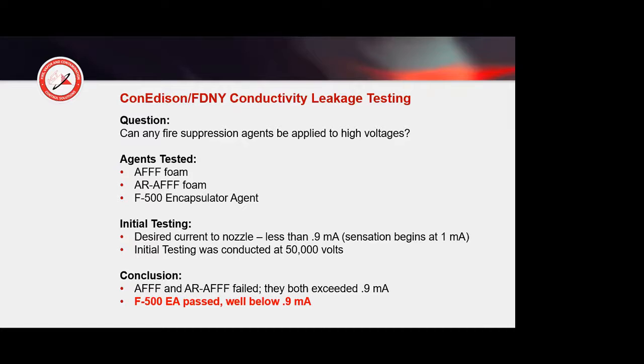When you put F500 into the stream at 3%, if you spray it on in a smooth bore fashion, the current will come back to the nozzle and it will kill you. If you open it up to a broken fog pattern where you have droplets and don't have a single pathway back, it was safe. So my friend Mr. Anthony Natali, it's a function of the spray pattern and not the agent.